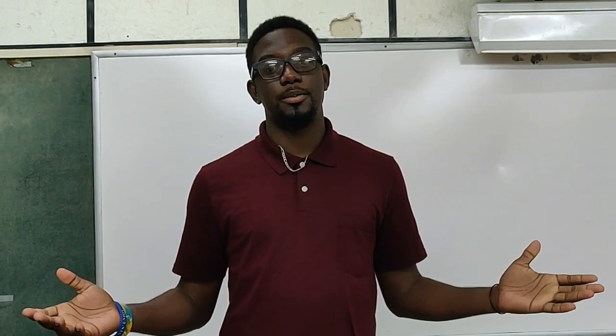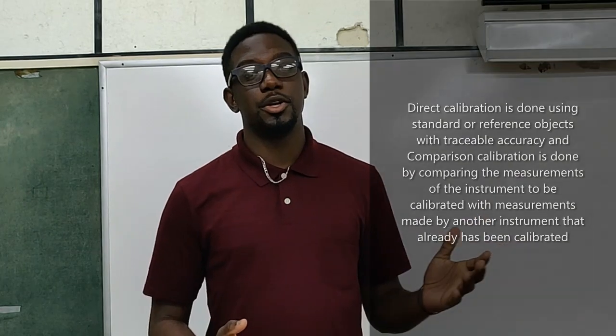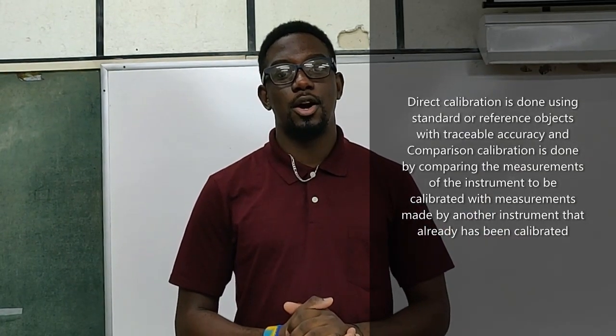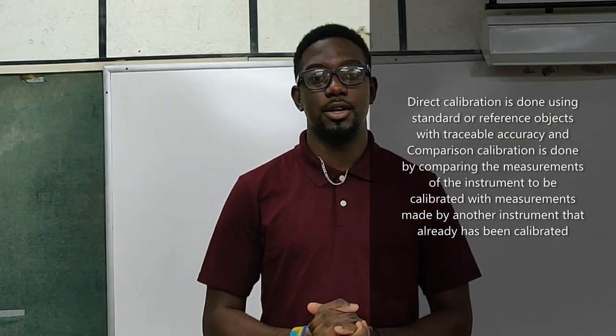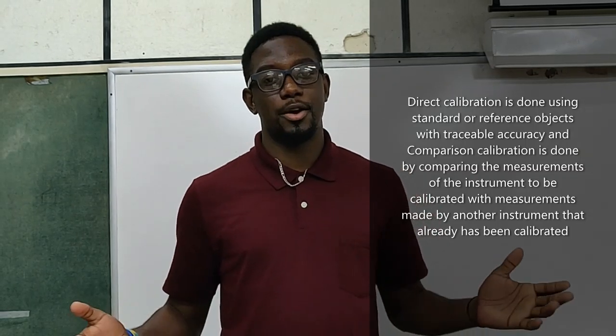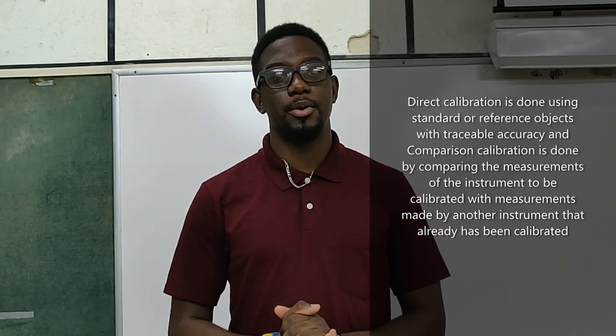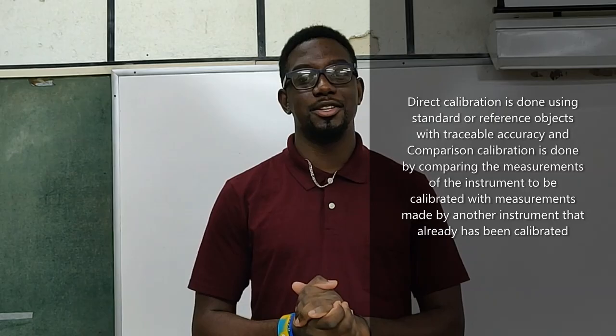We will be going through the two types of calibration and the standards of measurements used in calibration. Direct calibration, for one, is done using standard or reference objects with traceable accuracy. And comparison calibration is done by comparing the measurements of the instrument to be calibrated with measurements made by other instruments that are already calibrated.